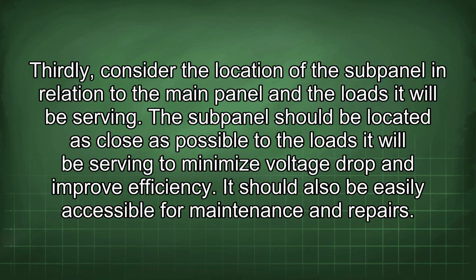Thirdly, consider the location of the subpanel in relation to the main panel and the loads it will be serving. The subpanel should be located as close as possible to the loads it will be serving to minimize voltage drop and improve efficiency. It should also be easily accessible for maintenance and repairs.